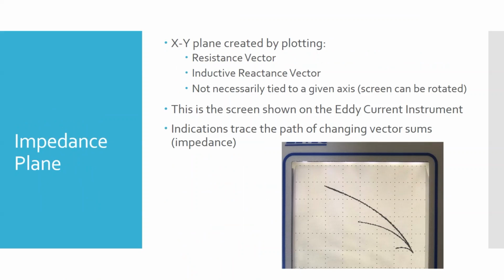We can set the origin where we want, but typically with cracks we put it in the lower right corner. As we go along, if we slide across a crack, it causes the inductive reactance and impedance to change, and as it changes, that point moves. Again, this is graphing that point's position over time, so it draws lines as you continue to move your part. If you stop, that's where the point stays; as you continue to move, it continues to move. What you get is that the size of the flaw is related to the size of the indication.